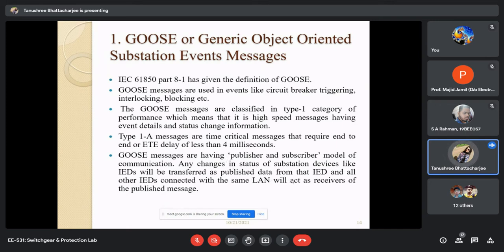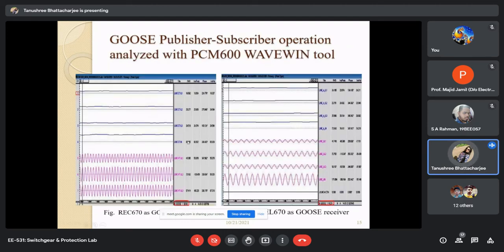Why publisher subscriber? Whichever IED senses a fault in its line or its breaker, that will be the publisher IED because it publishes the message, and all other IEDs connected to the same bay controller will be subscriber IEDs. So this is the type of message you can see.